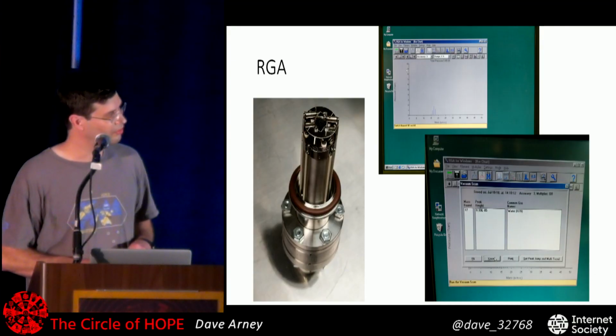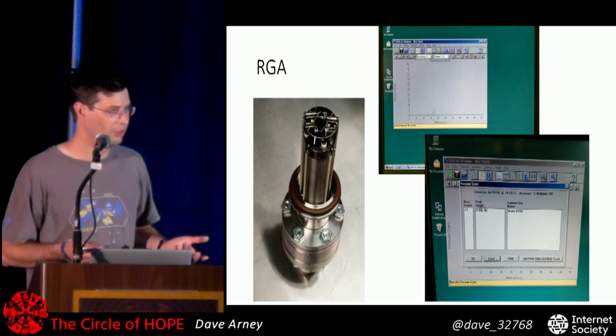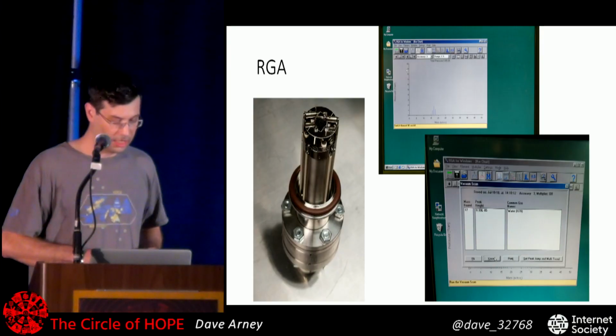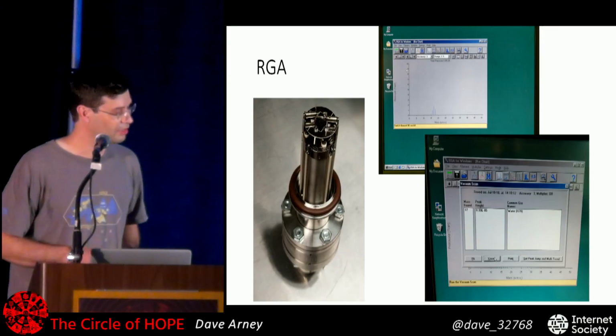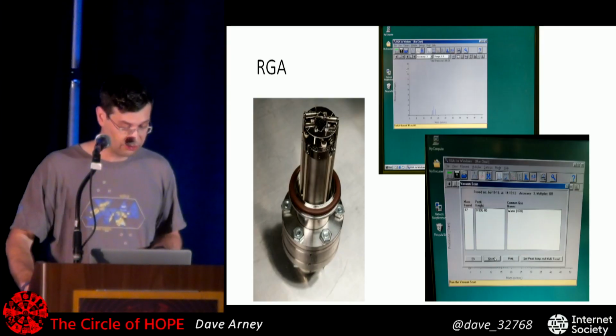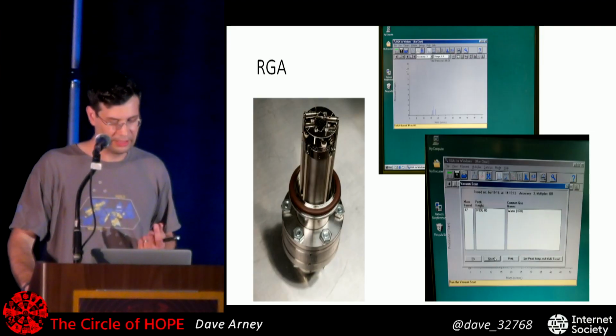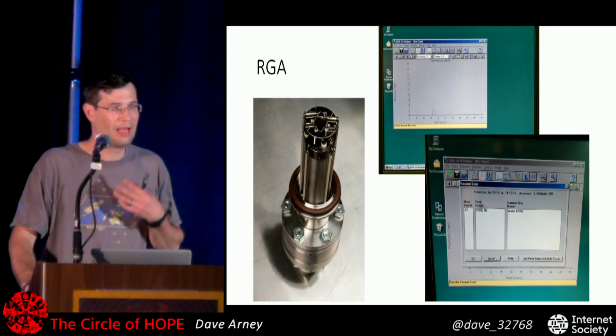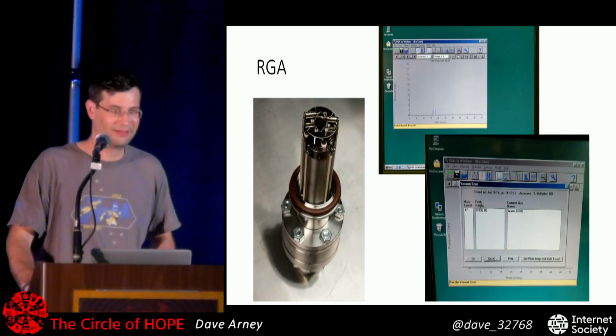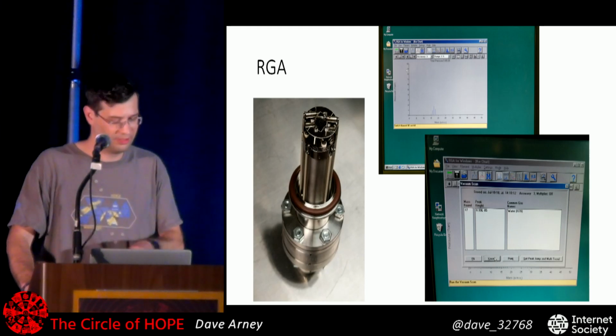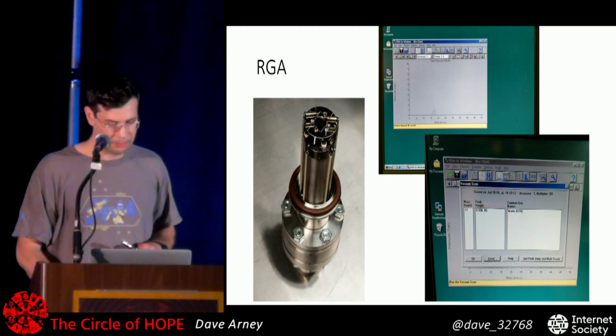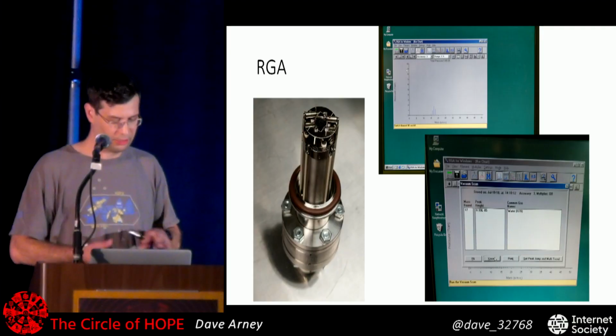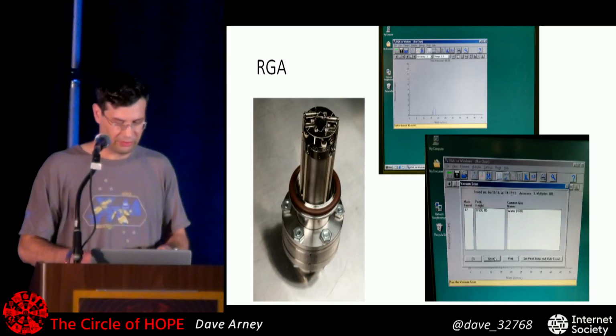Then there's some software that will analyze that and tell you, yeah, you've got water vapor in your system, and how much the partial pressure of that is. So this is really useful for telling what's going on in your system: how badly are things contaminated, is the whole thing full of oil that's backed out of your backing pump, or is it reasonably clean?